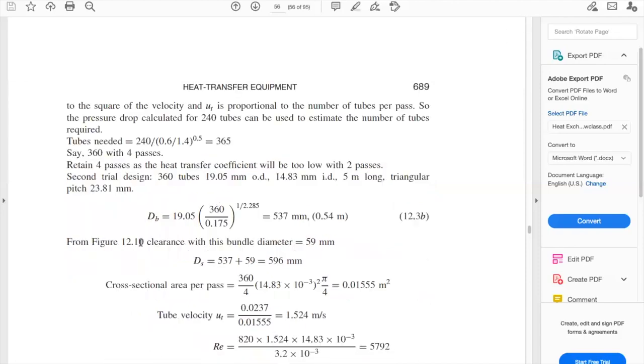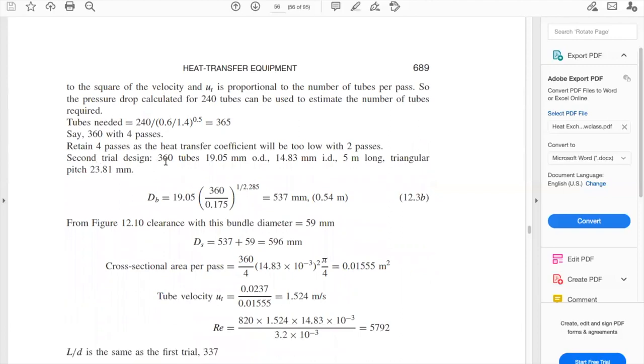We retain four passes, as the heat transfer coefficient would be too low with two passes. We are increasing the number of tubes from 240 to 360. Let's do the second trial design — we go back to step 6. Everything remains the same: the outer diameter, inner diameter, and length of the tube. We are not changing the tube specifications or the triangular pitch. Only the number of tubes changes.